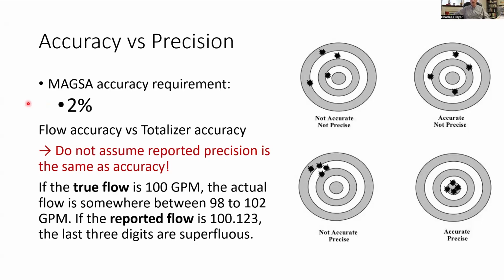Some of the meters that I mentioned earlier on, like the ultrasonic and the Venturi, are quite a bit more accurate than this. There are ultrasonic meters out on the market now that are accurate to within 0.025%. It's also important to understand that the accuracy of the flow rate is not exactly equal to the accuracy of the totalizer. The math behind this gets pretty complicated, and there isn't a big difference between the flow accuracy and the totalizer accuracy, but they are not identical. The totalizer accuracy is going to be a little bit worse than the instantaneous flow rate accuracy.